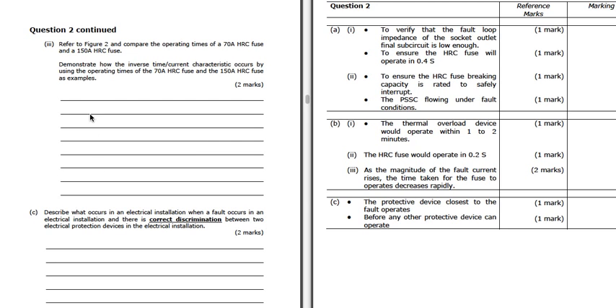Part 2. Compare operating times of a 70 amp and a 150 amp HRC fuse. Demonstrate how the inverse time current characteristic occurs by using the operating times of the two fuses as examples. So what we're saying there is, as the magnitude of the fault current rises, so as more current flows, the time taken for the fuse to operate decreases rapidly. So there's not an awful lot of difference between those two currents, but when you look at the time, the difference is much faster with the higher current. So higher current, much lower times to operate.